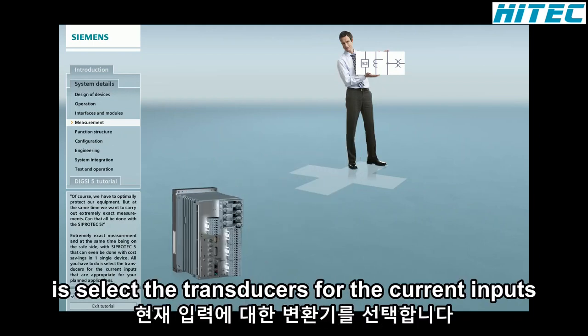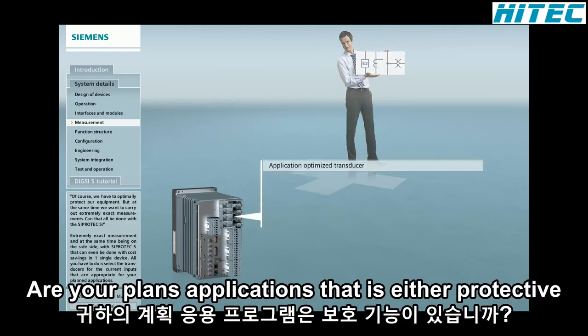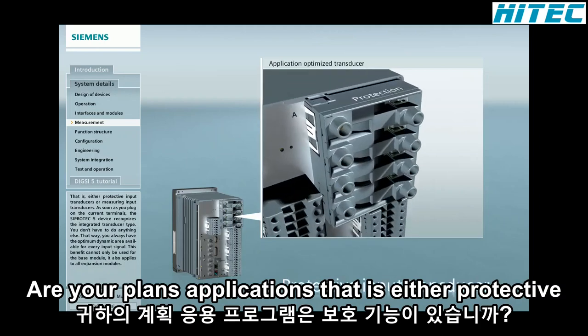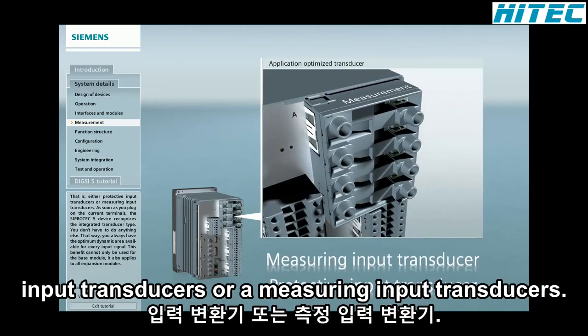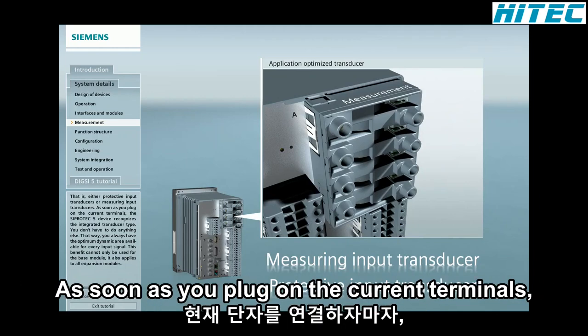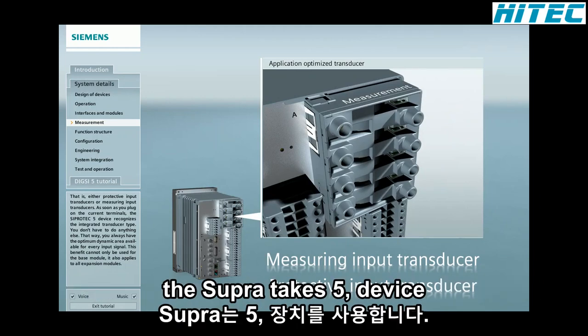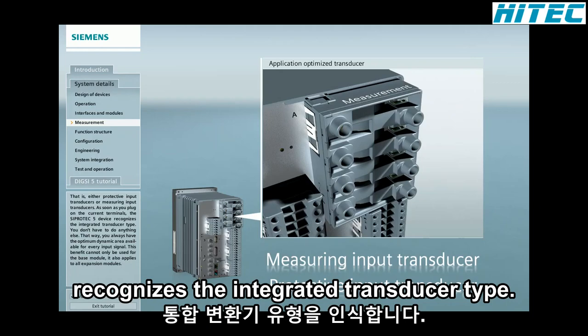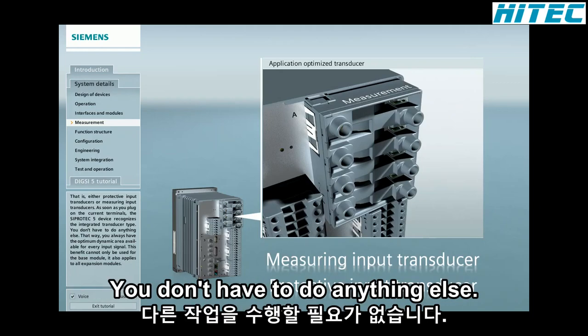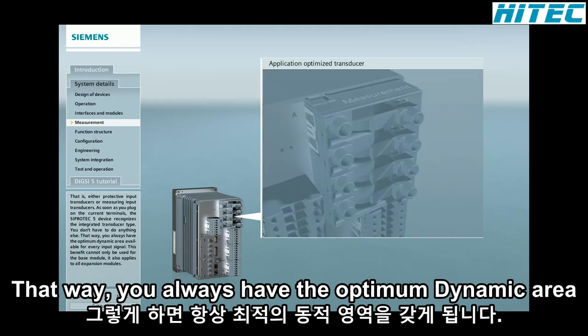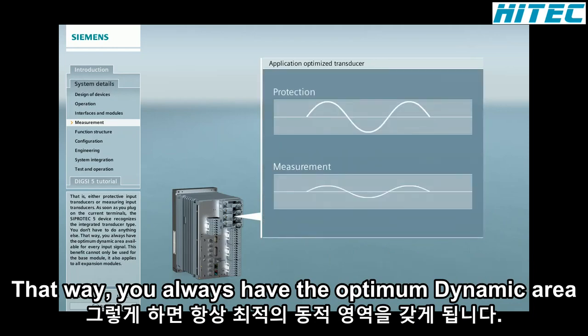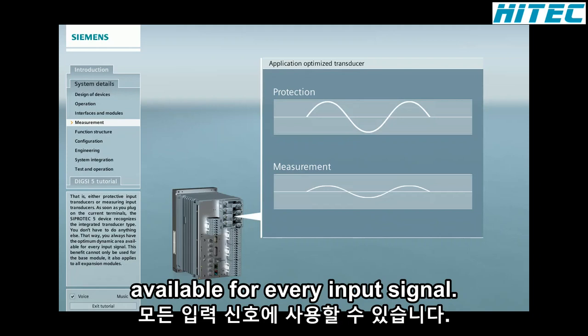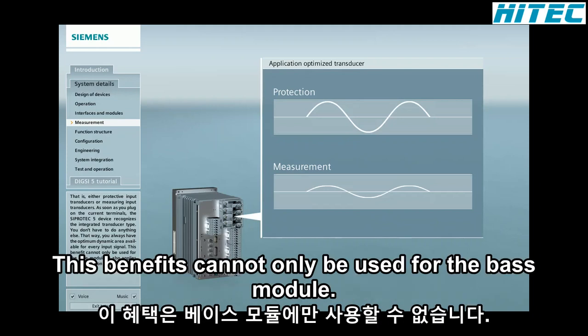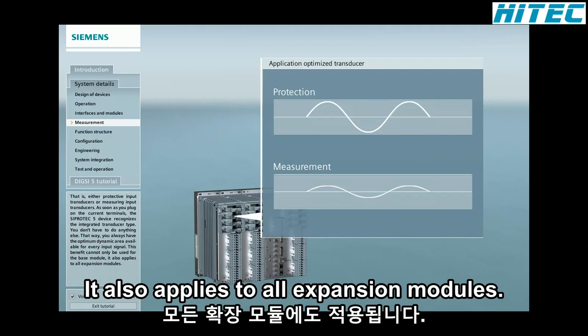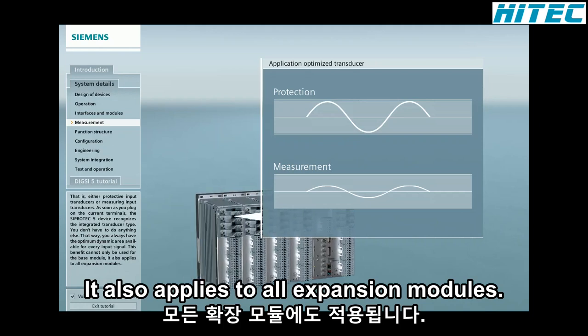All you have to do is select the transducers for the current inputs that are appropriate for your planned applications. That is, either protective input transducers or measuring input transducers. As soon as you plug on the current terminals, the SIPROTEC 5 device recognizes the integrated transducer type. You don't have to do anything else. That way, you always have the optimum dynamic area available for every input signal. This benefit can not only be used for the base module, it also applies to all expansion modules.